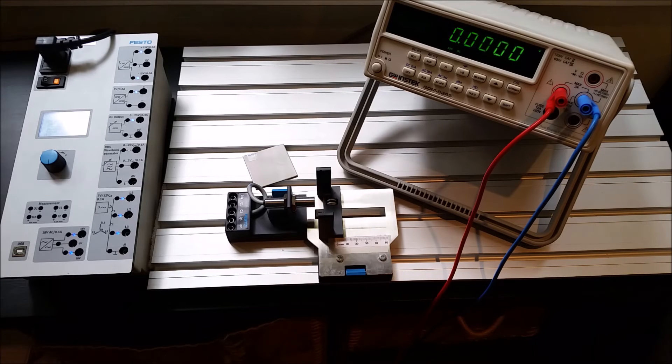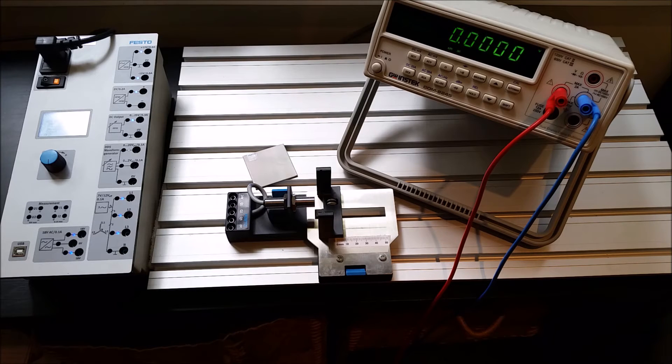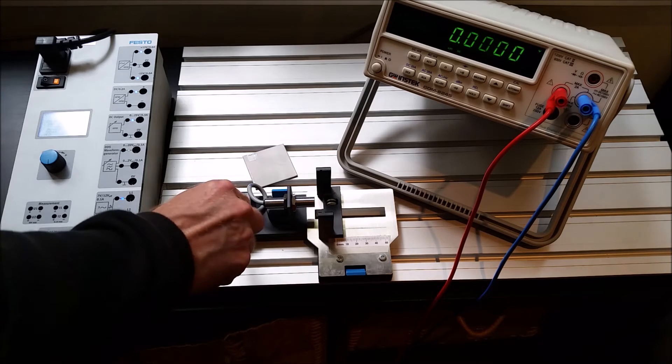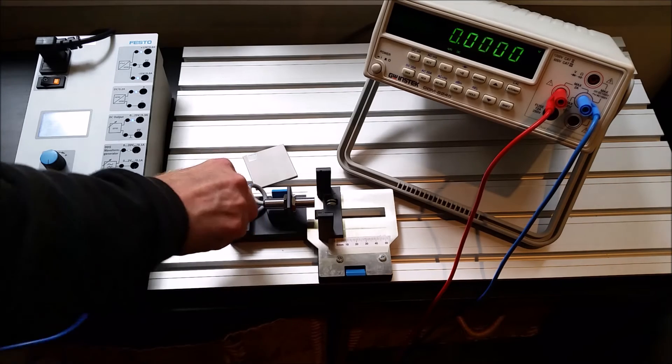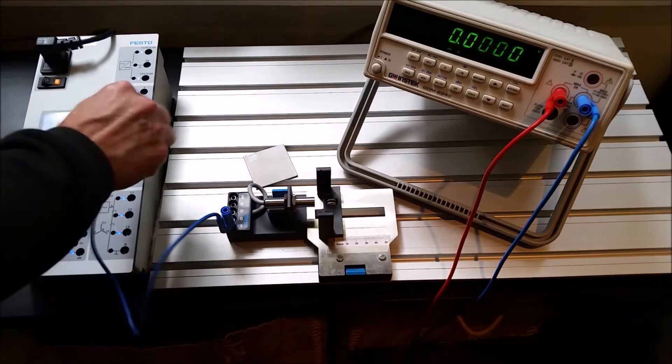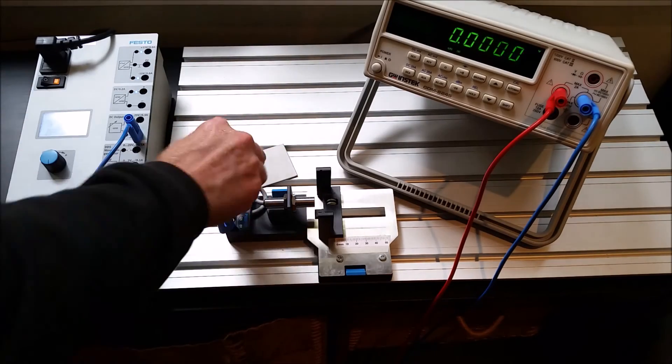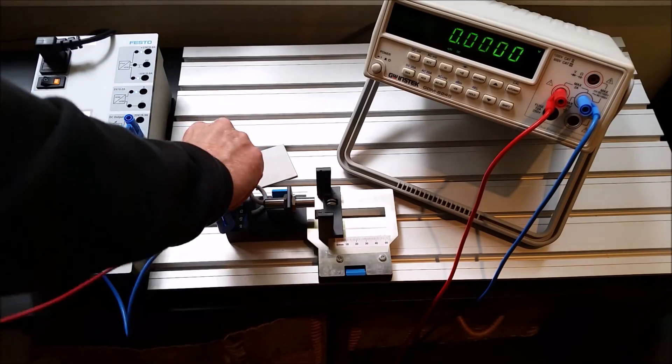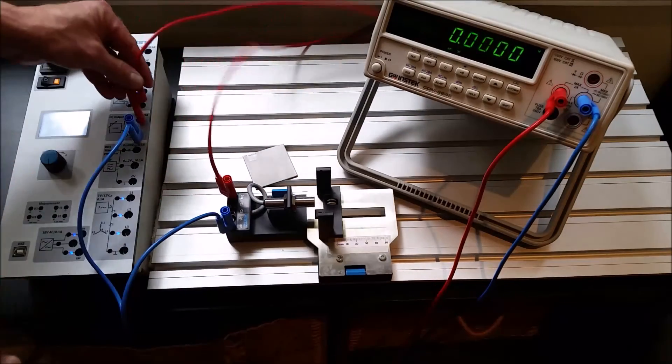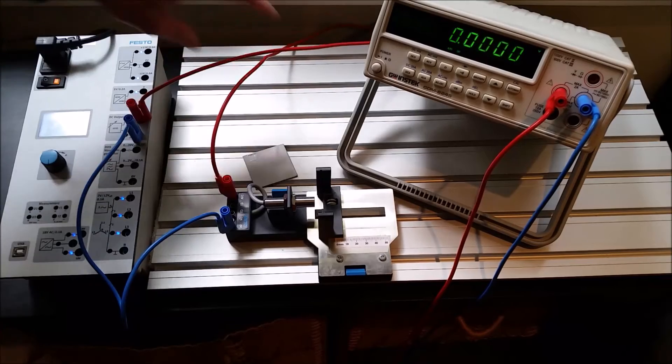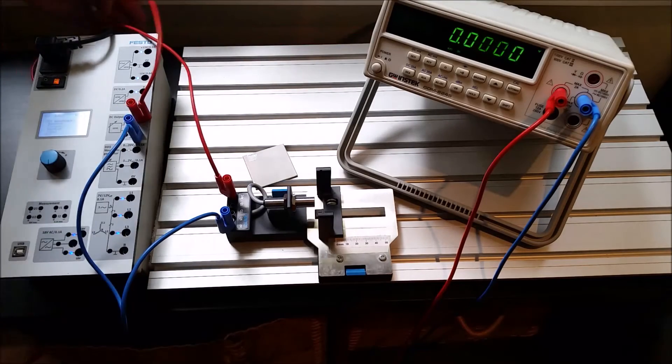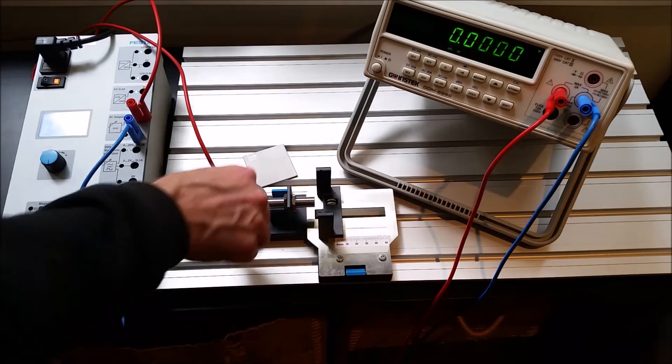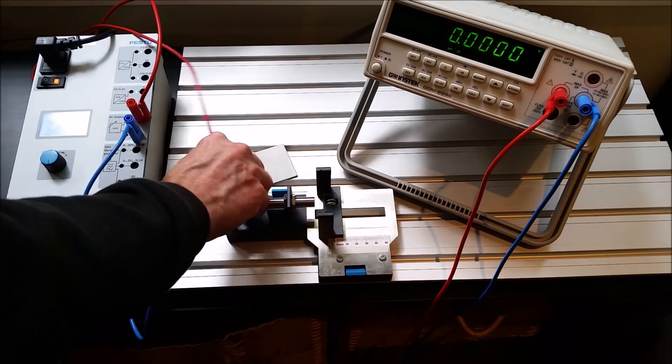Alright guys, so let's take a look at this analog inductive sensor. So we've got our 24 volts. Same as always, we're going to go 0 volts to your common, positive to your 24 volts. Out in the field, these guys are going to be the brown for the positive, the blue for the negative.